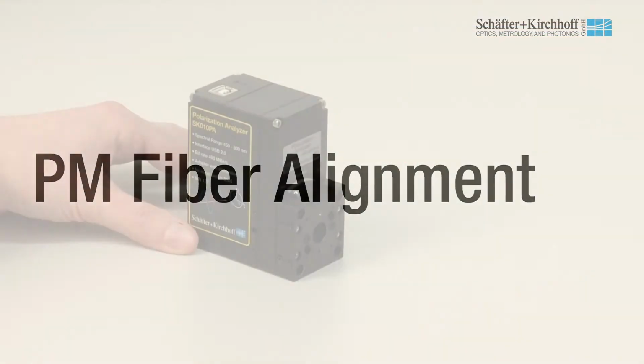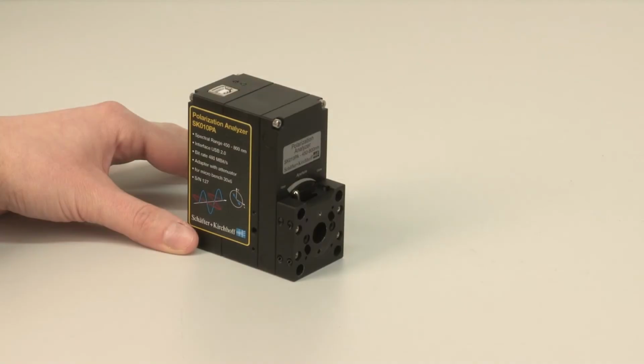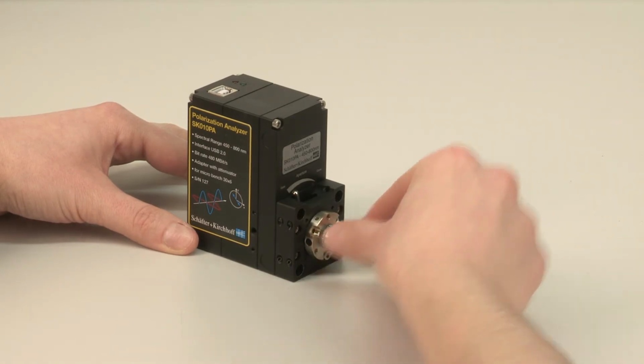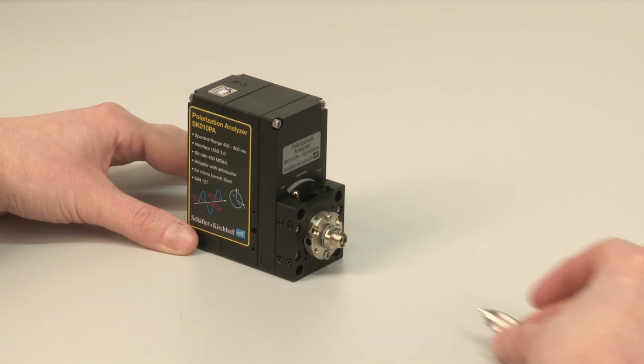One main application of the SK010PA Polarization Analyzer is the alignment of polarization-maintaining single-mode fibers with the polarization axis of the source. After mounting an adequate adapter, the fiber, for example of a fiber-coupled helium-neon laser, is connected to the analyzer.